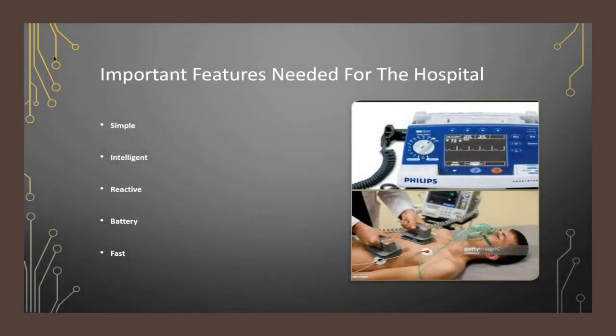Important features needed for the hospital. Simple: the module automatically turns on, which is clear and obvious with off-on buttons. Intelligent: sensors assess and correctly advise that a shock should be delivered at the appropriate time, personalized to every man, woman, or child based on body type. The device designed for adult defibrillation should have an energy setting of 50 to 360 joule. Responsive: the device can quickly distinguish when the user has completed a step and is ready for the next instruction.